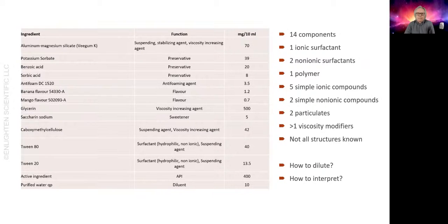I've explained the challenge of going from electrophoretic mobility to zeta potential. Even if you assume your zeta potential data are due to your drug particles and nothing else, how can you estimate your value of kappa and how can you estimate your value of a, the radius? Kappa requires knowledge of all of the ionic materials and their valences. If you look at the list, there are many ionic components. For example, the saccharin sodium - you need to know the dissociation constant under the conditions you're storing your sample. Does the surfactant fully ionize or is it only weakly dissociated? Is it weakly adsorbed onto the drug? There are many fundamental questions that you simply will not be able to answer.